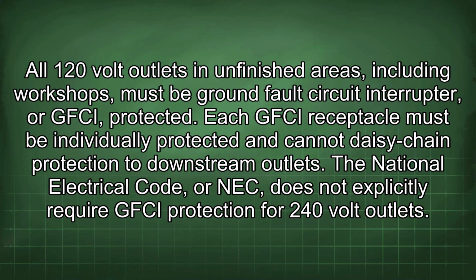All 120-volt outlets in unfinished areas, including workshops, must be ground fault circuit interrupter, or GFCI, protected. Each GFCI receptacle must be individually protected and cannot daisy-chain protection to downstream outlets. The National Electrical Code, or NEC, does not explicitly require GFCI protection for 240-volt outlets.